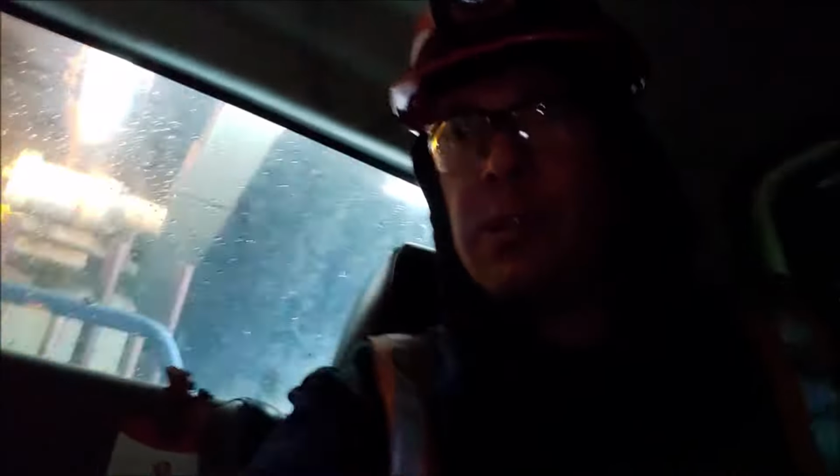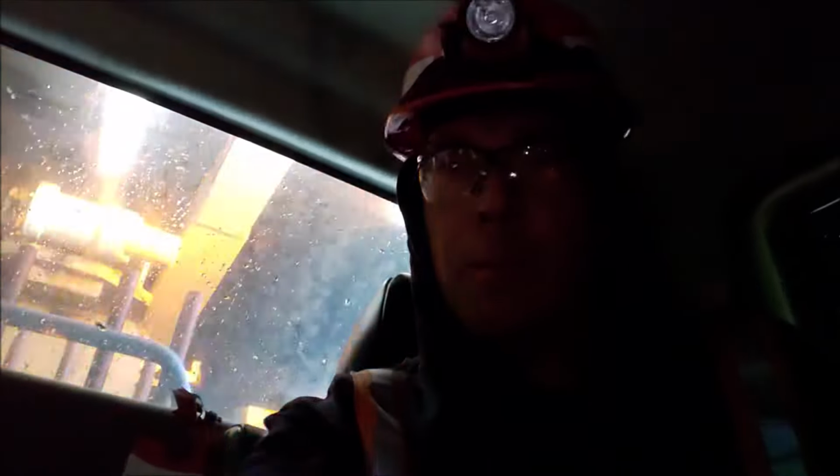It's quite a long line, so I'm not feeling real good about this, but we're gonna go ahead and refuse the single phase sideline and close her in. Hopefully she stays in. If it does stay closed in, I'll take my thermocam and run the line with that, see if we can't find an insulator heating up or something.